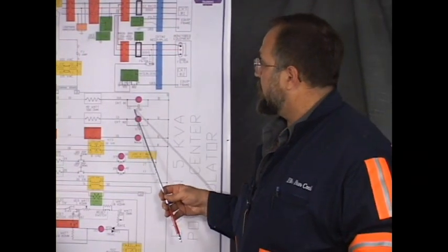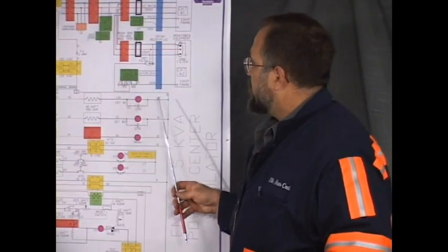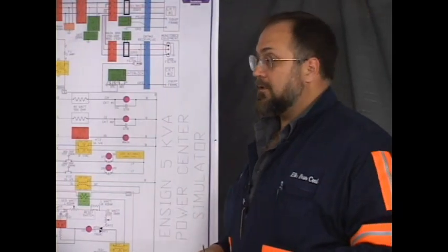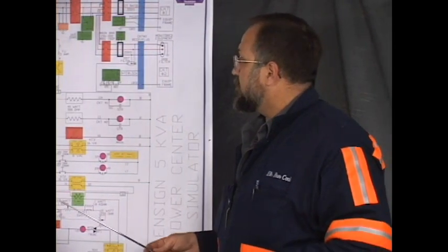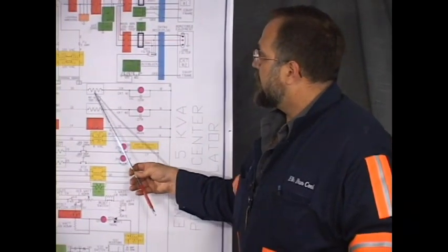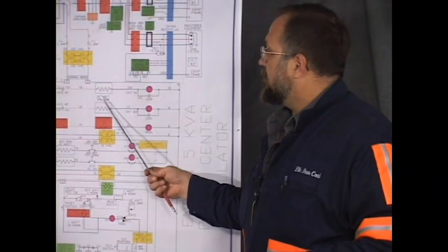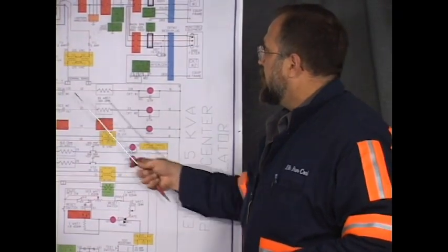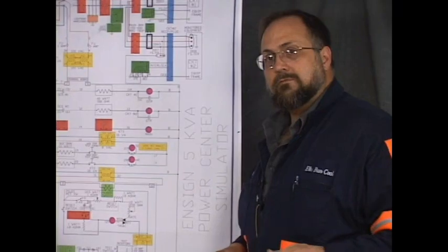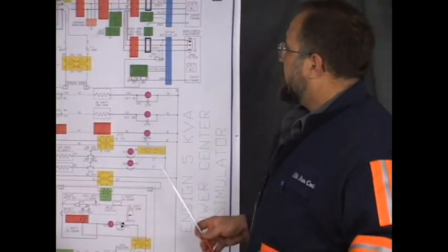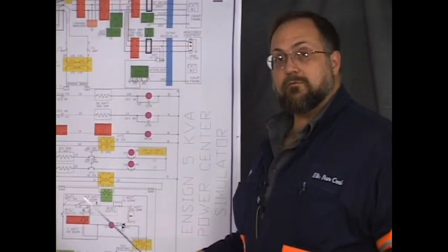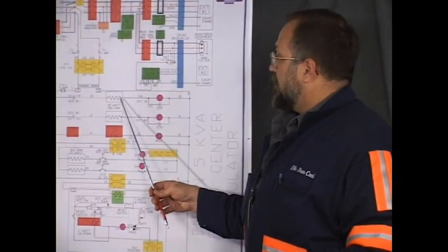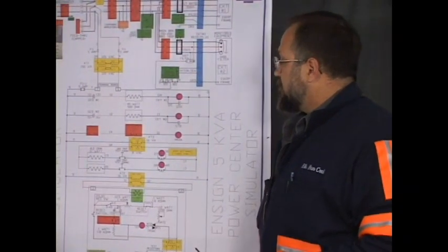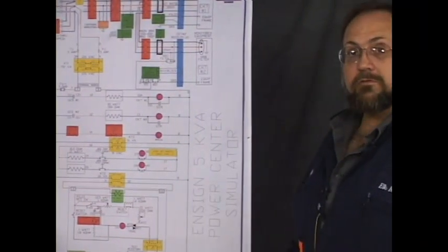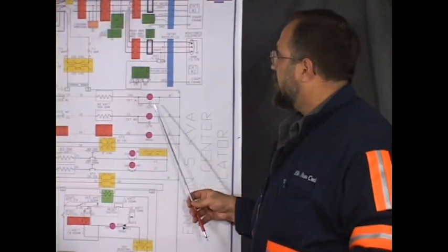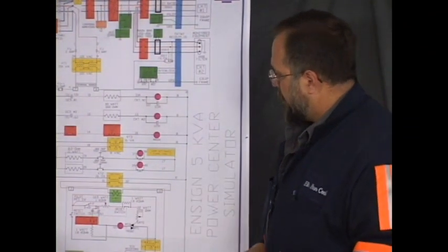Now, when we close GTR, instead of it being a short, the current being very high due to a short circuit, we have a load. And this load limits the amount of current that flows and preserves this fuse. Now, the only time that all of the control voltage is dropped on the 40 watt 500 ohm resistor is when the GTR is closed. The GTR, ground trip relay.